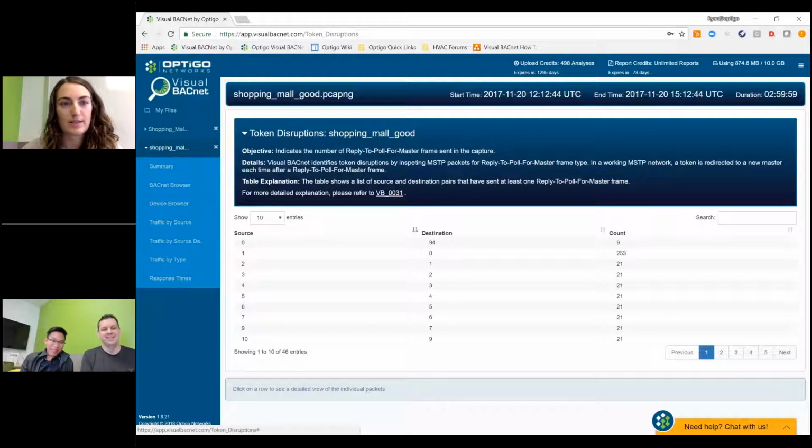So your device configuration is completely... either that, so there could be a couple of things in this file. Do you think they're in a star topology? It's hard to say. It could be that. There could be an extra capacitance on the wire. At this point, if you came back to us and said this is truly wired in a daisy chain fashion on a straight 2-wire network.